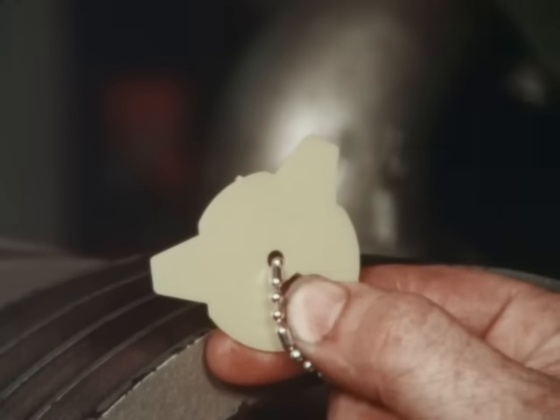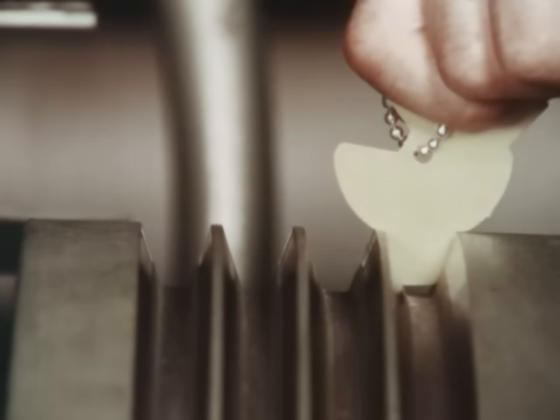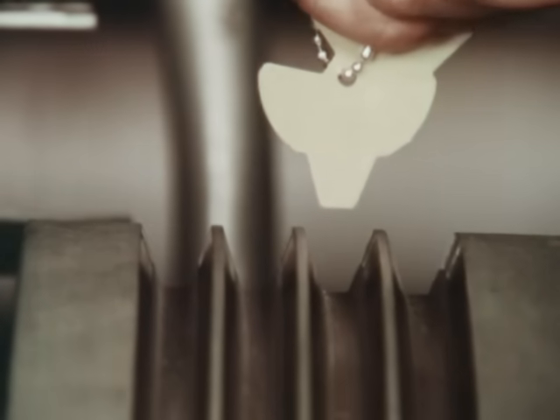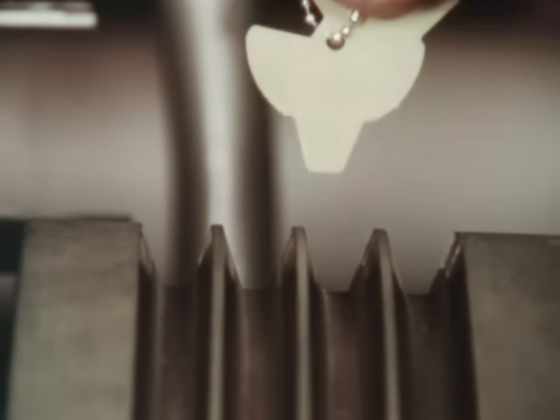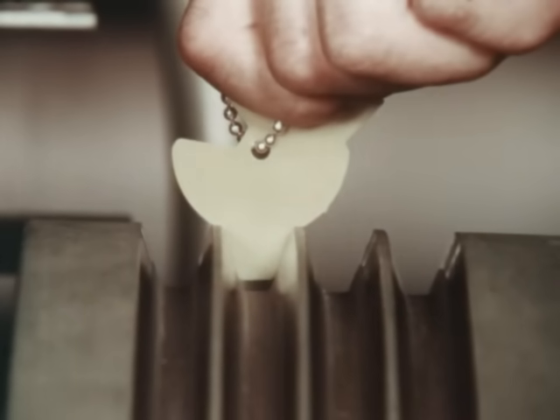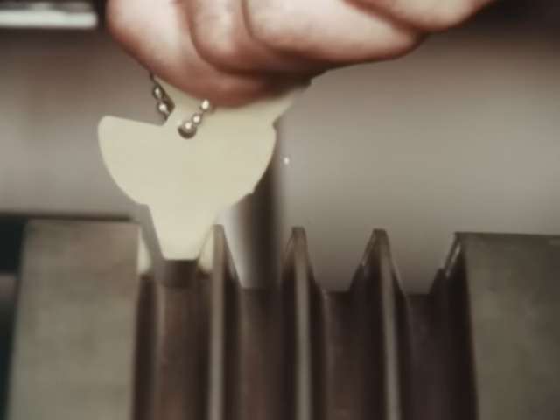To check for sheave groove wear, use a sheave gauge. Select the proper gauge according to the sheave diameter and insert it into the groove. The gauge rim should rest on top of the outside diameter of the sheave, and the inside should lie flush against the side wall of the groove. On multiple belted drives, be sure to check all the sheave grooves for uniformity.